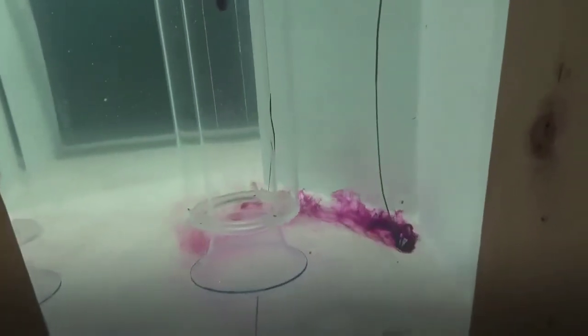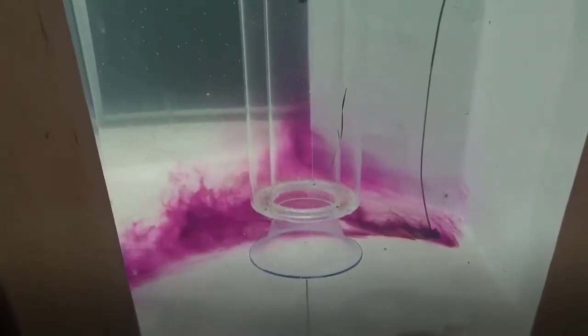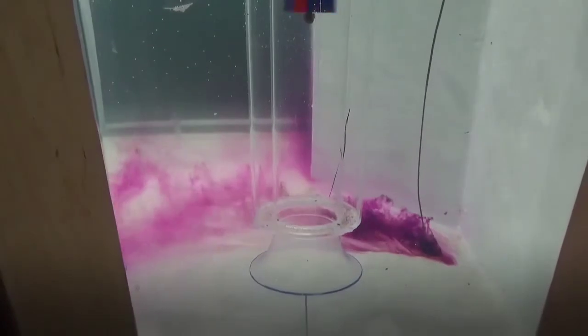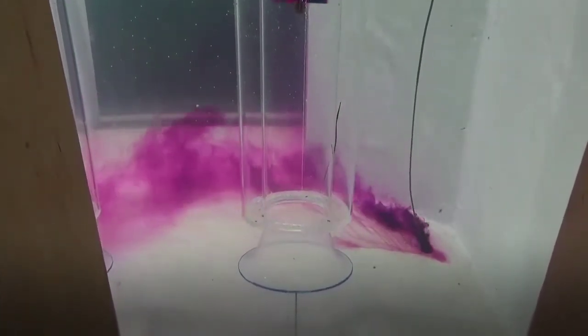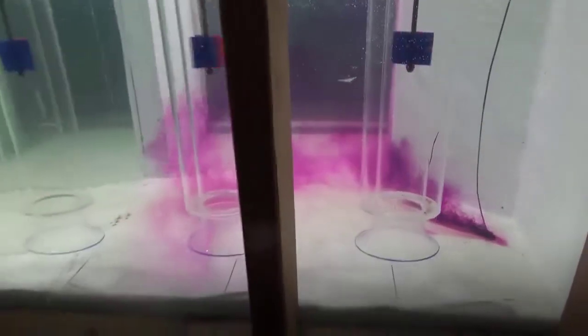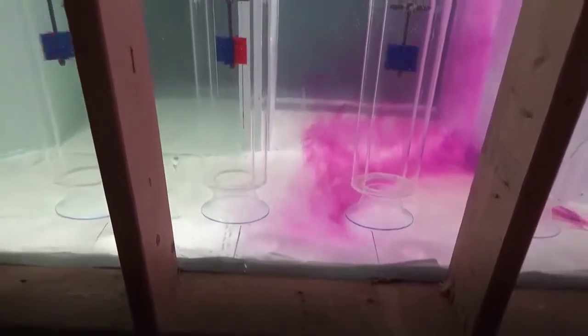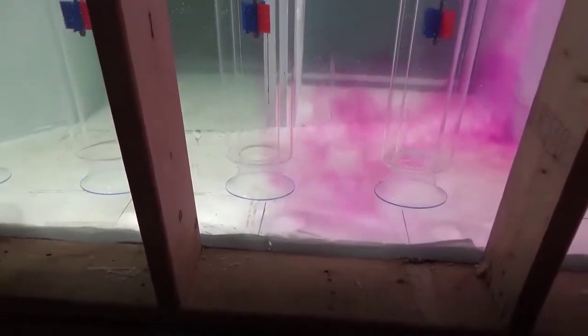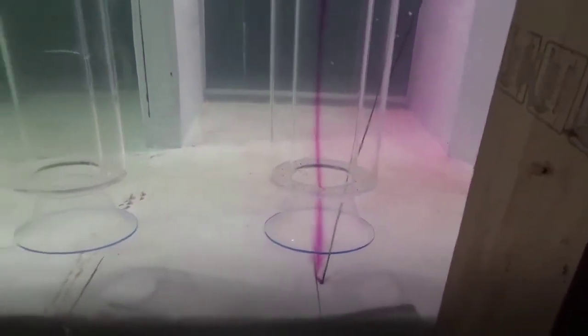Let's go ahead into this corner here, and you kind of see that upstream flow from the backside here, going right up towards the front. You see it going right out the front. If you watch that, and then it wraps itself around to this pump. Let's go ahead and come over to the next one. We'll hit 3 of them here. There again, very, very well organized vortex activity. Let's go to the center pump.